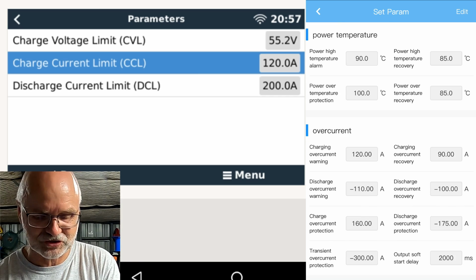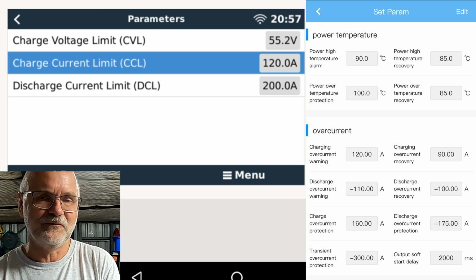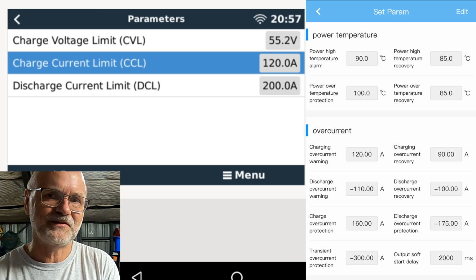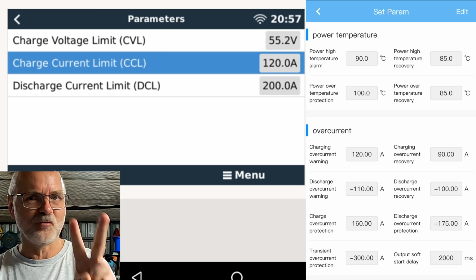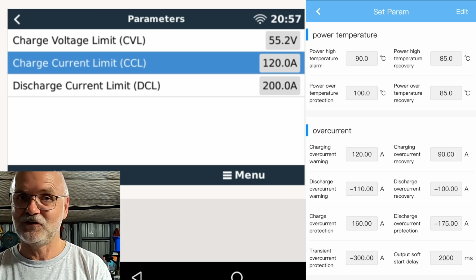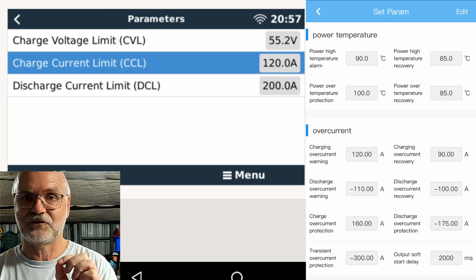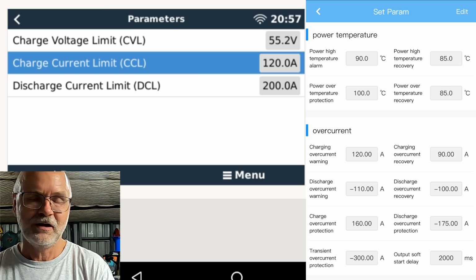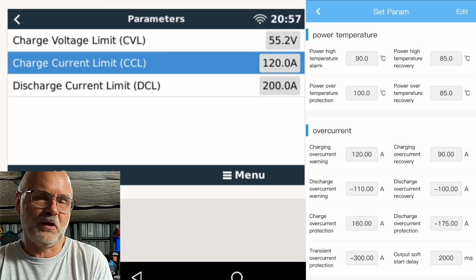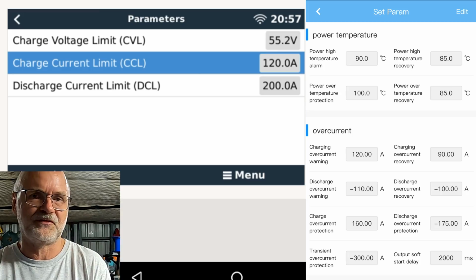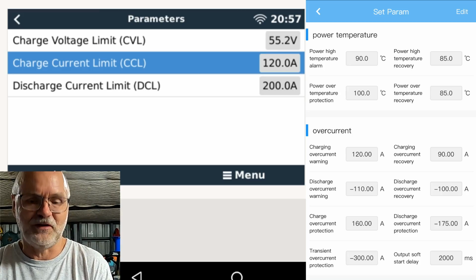Because remember, it was the 120 amps we have set here for the charging overcurrent warning divided by 2. And then we had 60 amps. But now we have 2 batteries in parallel, and the BMS knows that because we set the dip switches accordingly and connect the other one via RS485. It actually doubles this because it thinks, well, every battery can deliver these 60 amps, so make it 120, right?